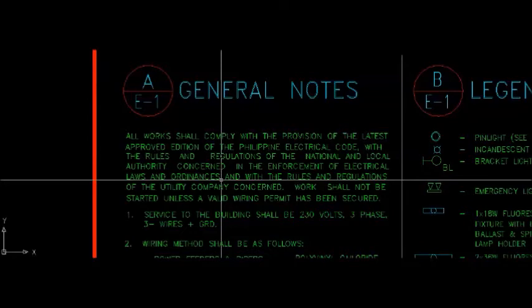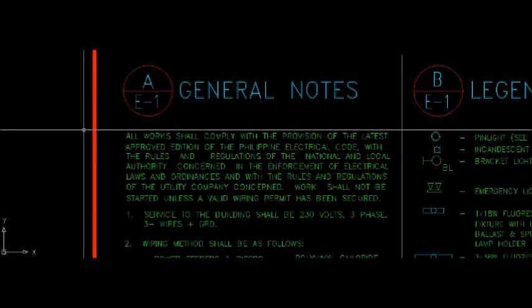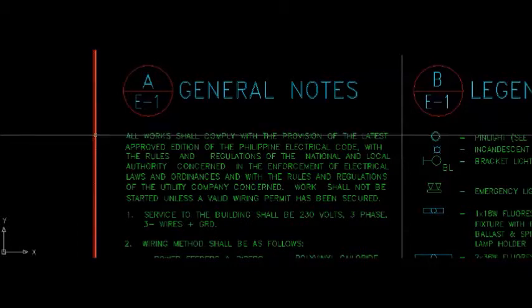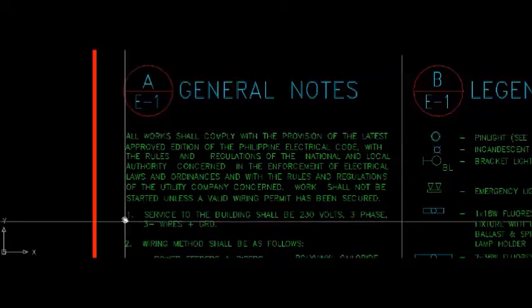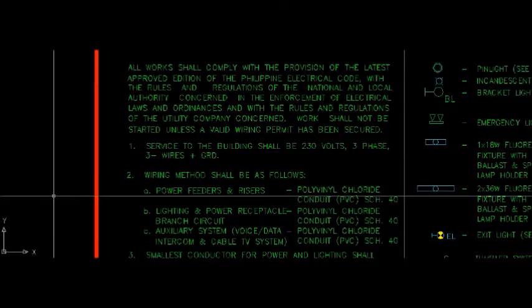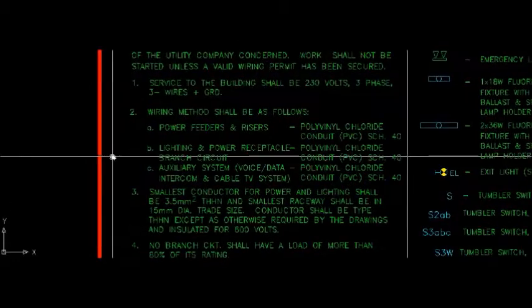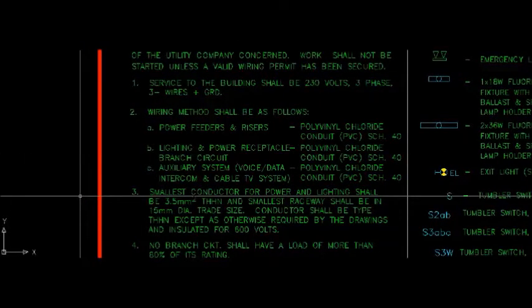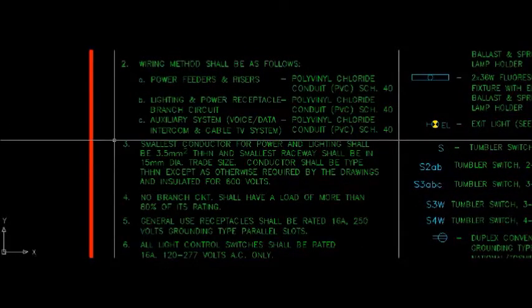Electrical plan. General notes. All work shall comply with the provision of the latest approved edition of the Philippine Electrical Code with the rules and regulations of the national and local authority concerned in the enforcement of electrical laws and ordinances and with the rules and regulations of the utility company concerned. Work shall not be started unless a valid wiring permit has been secured. Service to the building shall be 230 volts, 3-phase, 3 wires, plus GRD. Wiring method shall be as follows.